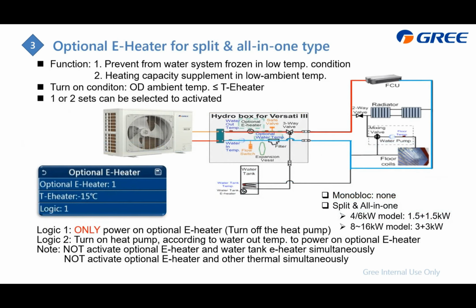As for the optional heater, the working logic is similar to other thermal. And what you can set is when we detect the outdoor ambient temperature is lower than your setting, this one, then we will turn on the heater, and you can turn on 1 or 2 sets. And also here is the logic 1 and 2.